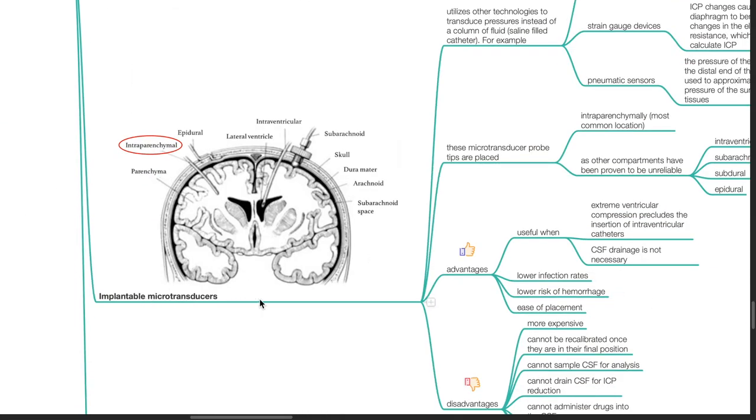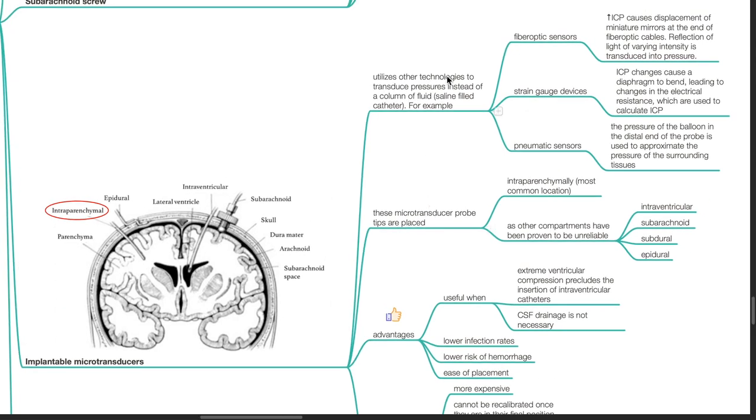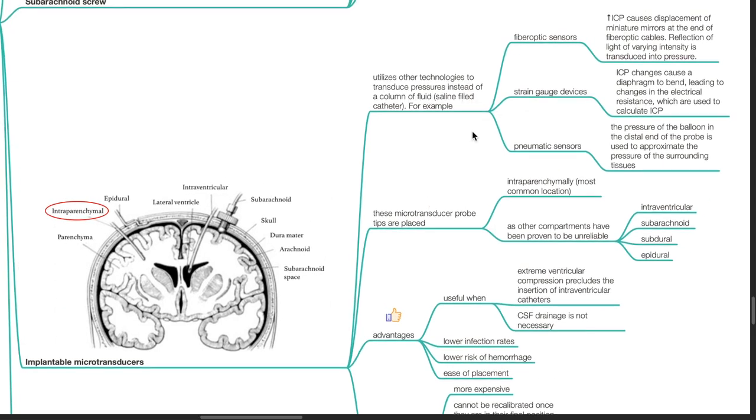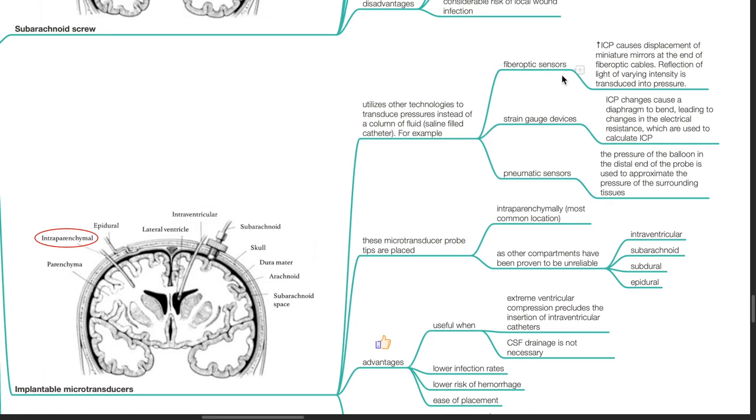Implantable microtransducers. It utilizes other technologies to transduce pressures instead of a column of fluid. For example, fiber optic sensors, strain gauge devices, and pneumatic sensors. Fiber optic sensors: raised ICP causes displacement of miniature mirrors at the end of fiber optic cables. Reflection of light of varying intensity is transduced into pressure. Strain gauge devices: ICP changes cause a diaphragm to bend leading to changes in electrical resistance which are used to calculate ICP. Pneumatic sensors: the pressure of the balloon in the distal end of the probe is used to approximate the pressure of the surrounding tissues.